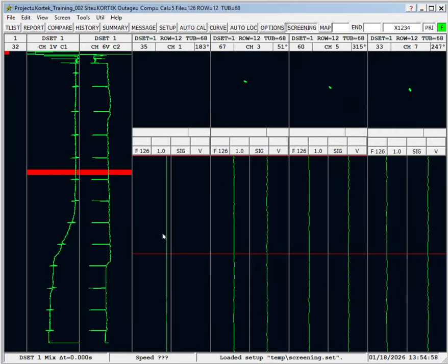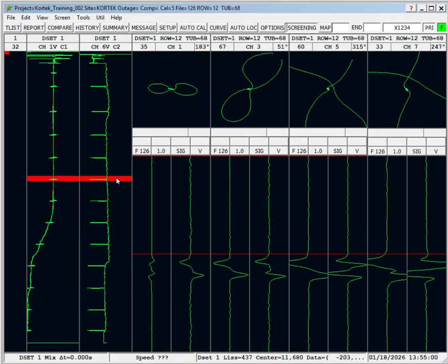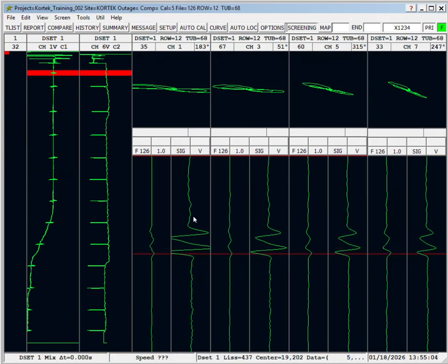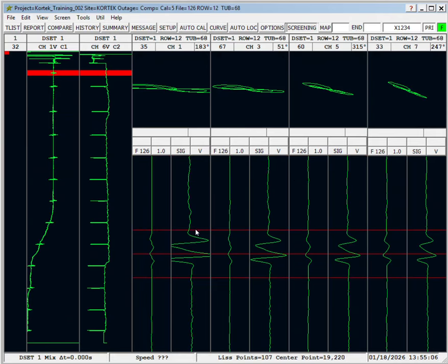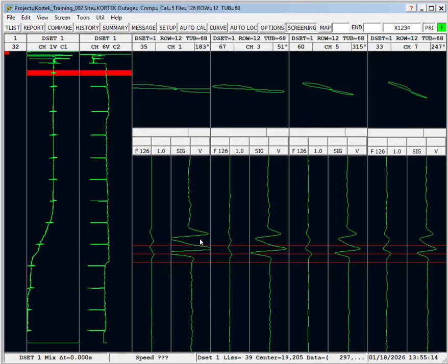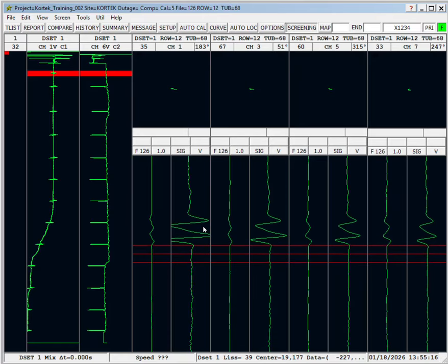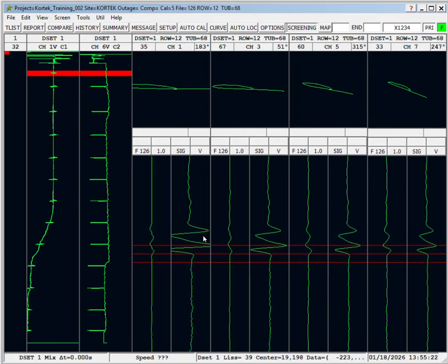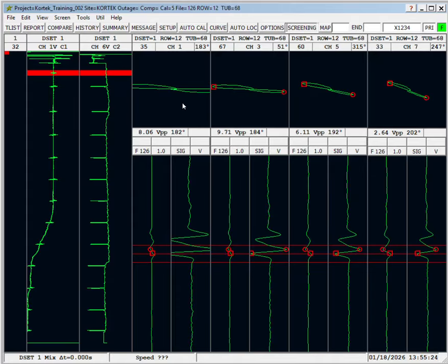We'll go pull up another tube here. Space bar to balance. You see a bunch of tube support plates. There you got another set of paired dents. Now, they're not always in pairs. Very common to see just one dent signal. Now, this is actually a lot cleaner looking dent signal than we've seen before. Starts to the left, goes back to null. Other half of the differential coil pair sees them, goes to the right, back to null. Not a lot of rotation between the different channels.